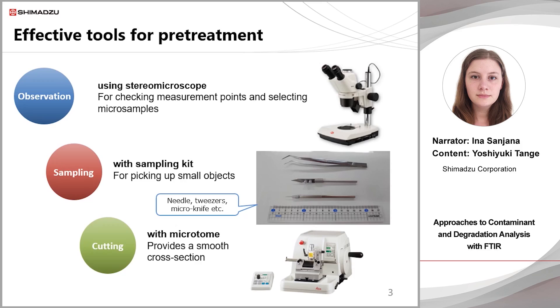This slide introduces effective tools for checking the condition of contaminants and collecting them for FTIR measurement. With a stereomicroscope or magnifying glass, it is possible to check measurement points in more detail and to select microsamples. A sampling kit, including tools such as tweezers or a micro-knife, helps handle very small objects. A microtome is particularly useful for getting a smooth cross-section.